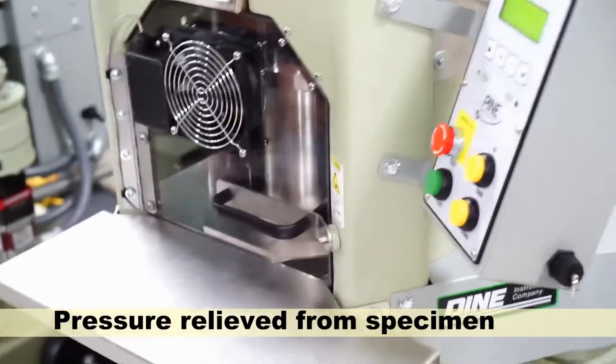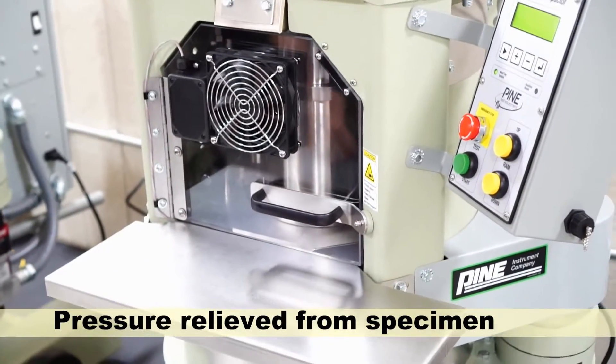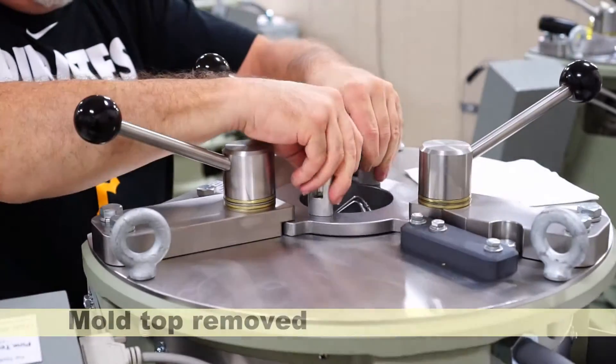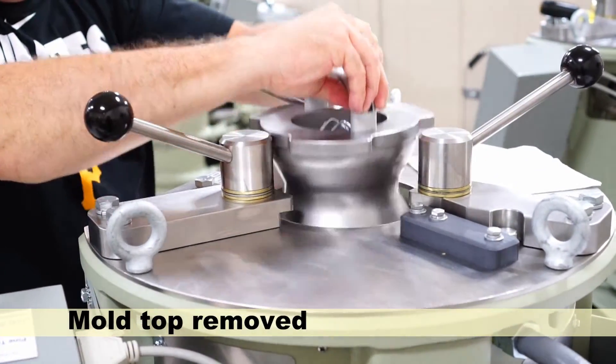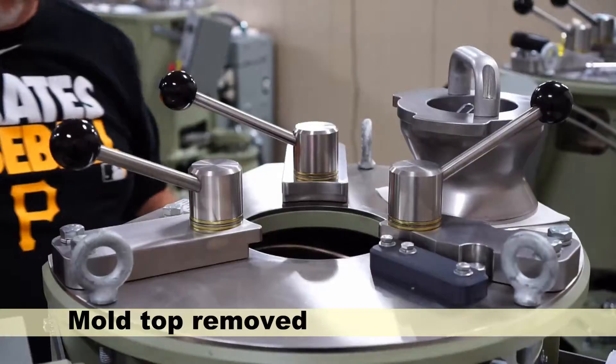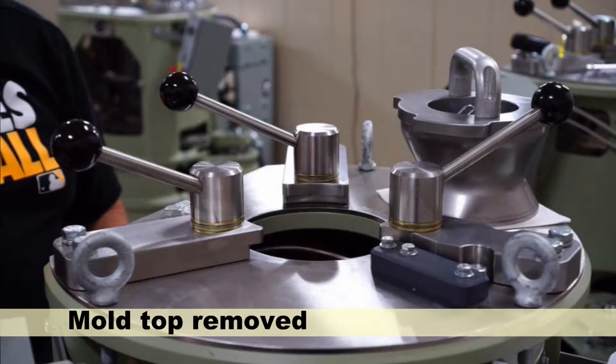When the desired number of gyrations has been completed, the compaction will stop and the machine will relieve the pressure from the specimen. The operator then removes the mold top to prepare for extrusion of the specimen.